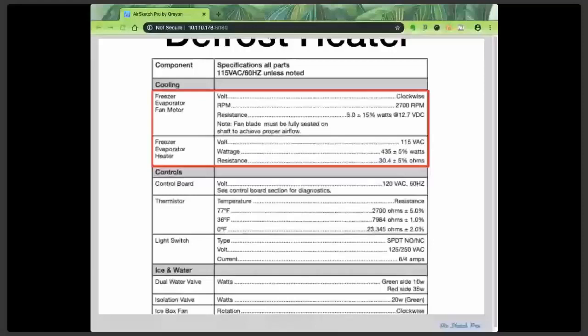But good techs know not to rely on ohms readings to declare an AC component good. The reason is that if the ohms read open, infinite resistance, or way out of spec, then yeah, you've found a problem. But if the ohms read good, that doesn't necessarily mean the component is good. You can't declare that at that point.